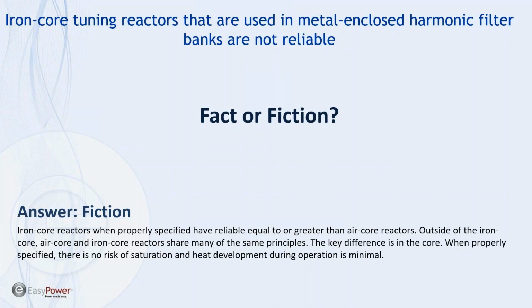Another point to be made is that iron core reactors in many ways are built in the same fashion as air core reactors. The only difference is the iron. In an air core reactor, they wrap the winding around an aluminum structure, and air is the magnetic path for the magnetic field. For an iron core reactor, the winding is wrapped around the core rather than around that aluminum structure, and the iron forms the structure, but it also provides a path. Both the iron core reactor and the air core reactor are posted up on insulators, so the insulators bear the primary voltage stress in the system.